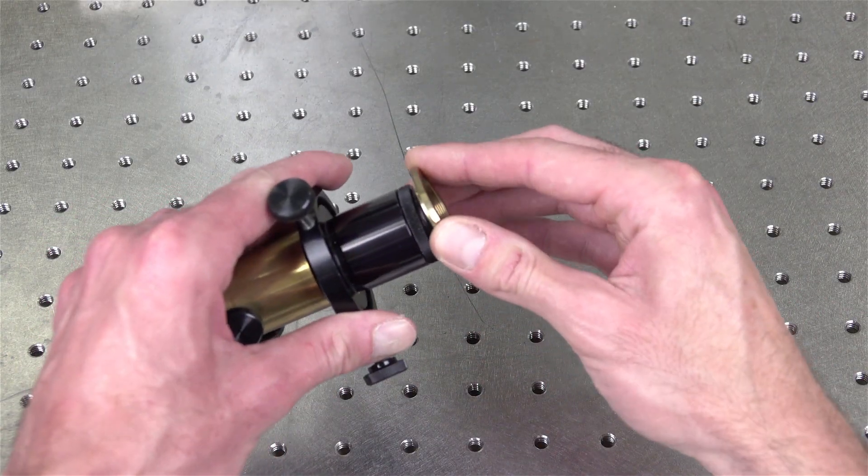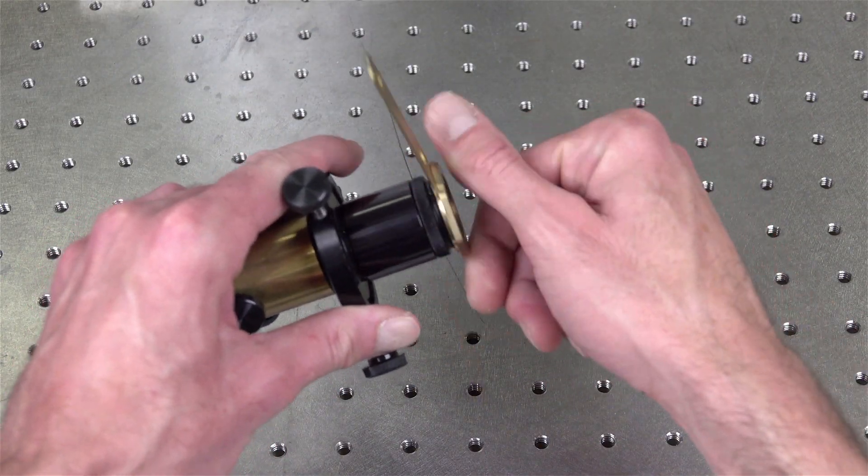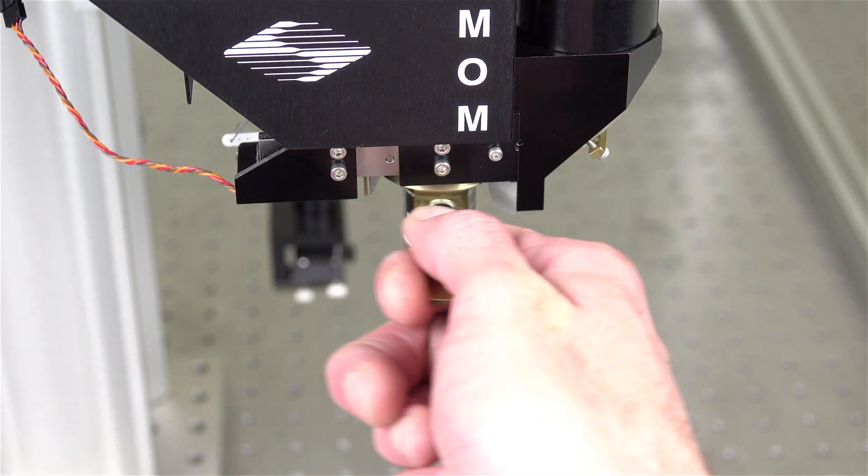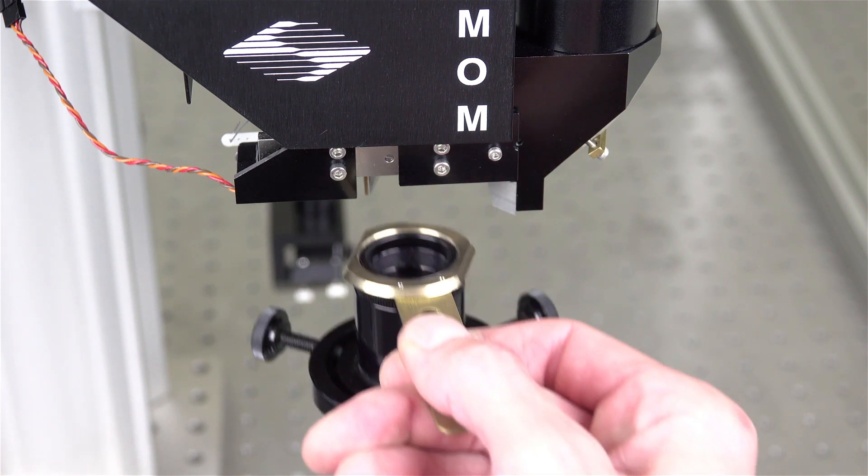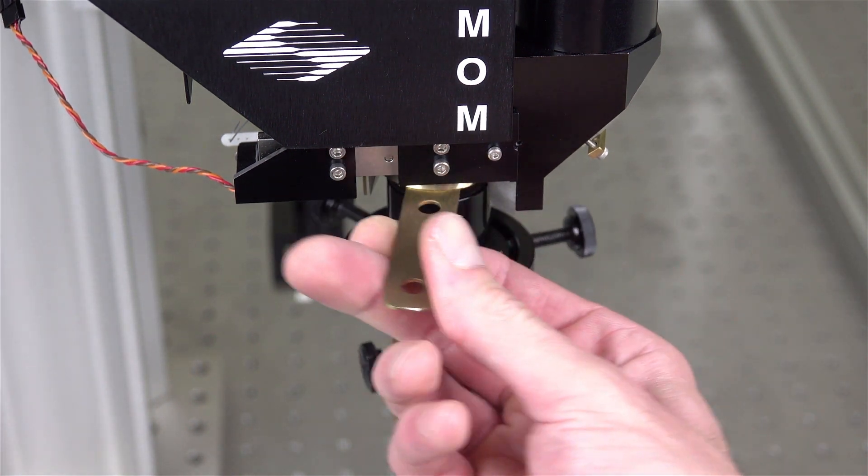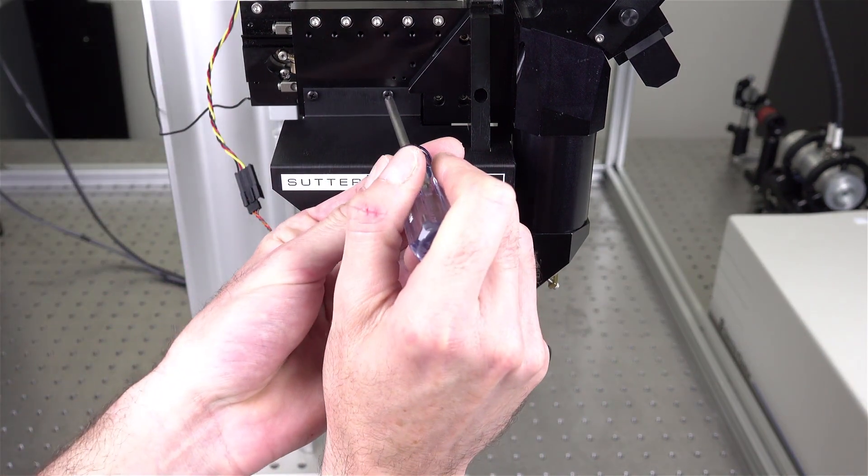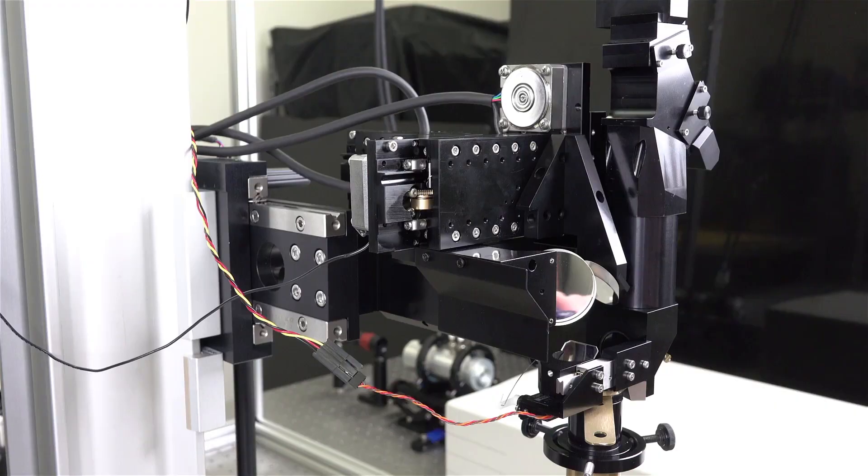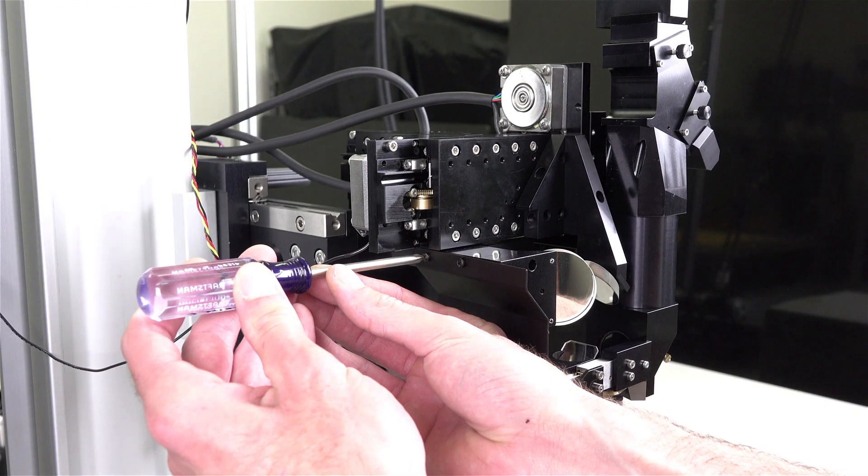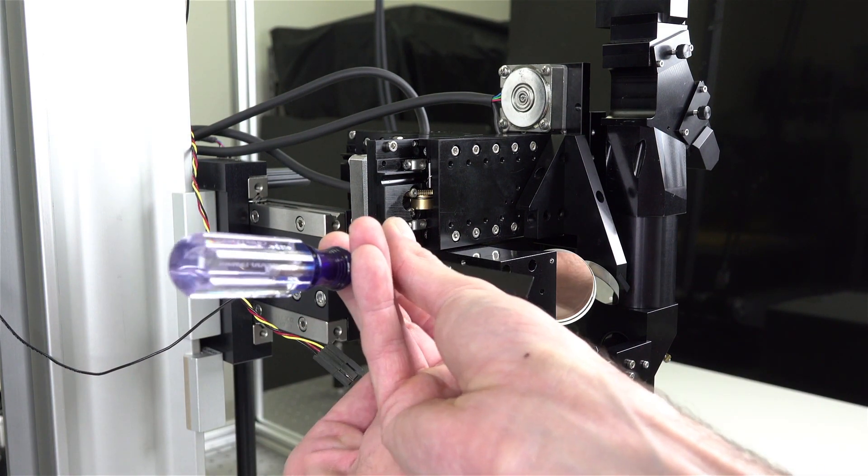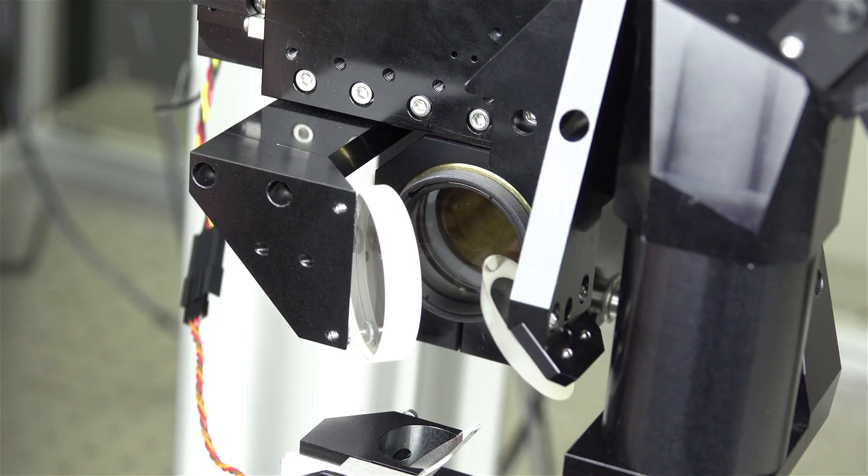Step 1: Assemble the alignment tool with the objective holder so it can replace the objective in your system.